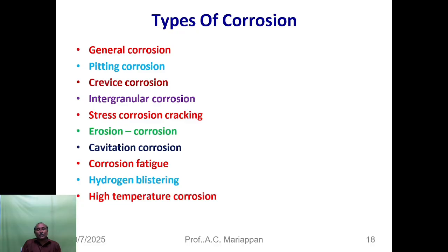Sometimes the equipment is also affected by a combination of erosion corrosion and cavitation corrosion, corrosion fatigue, and hydrogen blistering, which is called HIC, hydrogen induced crack. The metal will blister on the inside surface; it will not occur outside, it will occur inside the equipment on the surface of the wall. By visual inspection, metal blistering can be observed. If you break the blisters, nearby successive blisters are joined together by intergranular cracking, the grain structure of the material joined together.